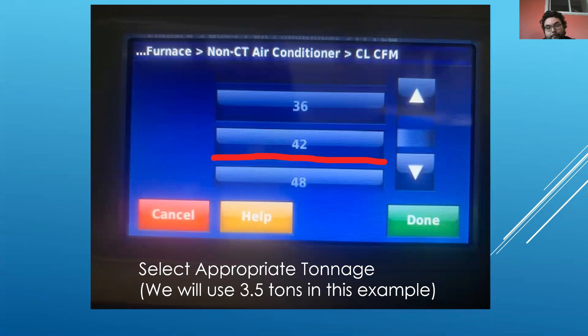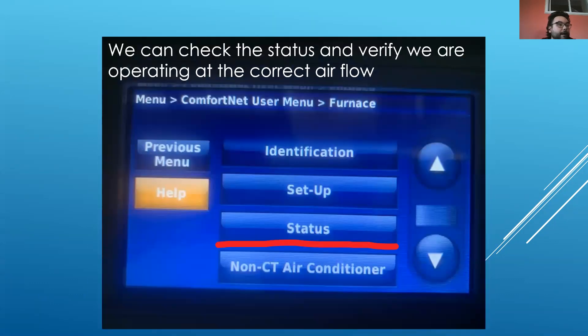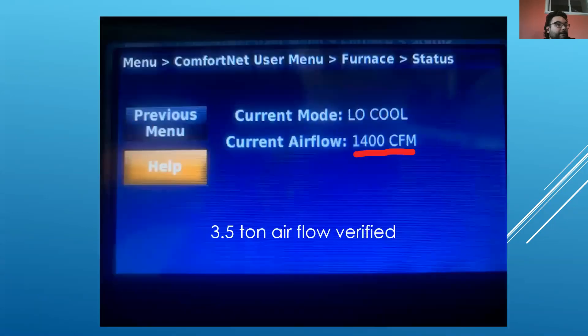In this example, we have a three and a half ton air conditioner, so we'll click on 42 for 42,000 BTUs. We can then go to the status option, which is right above non-communicating air conditioner, to verify we have the correct airflow. We click on status and it shows our current airflow is 1400 CFM — confirming we have three and a half tons of airflow.